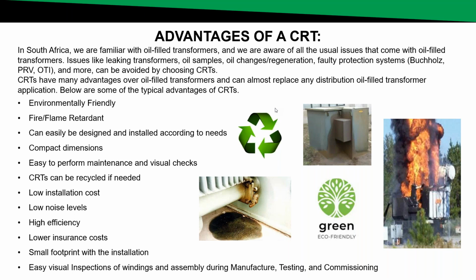Cast resin transformers are designed and manufactured to be flame retardant. As I've discussed, most cast resin transformers carry the F1 rating, which means they do not burn. I have even experienced personally where a complete installation has burned down. However, the actual cast resin transformer is still intact. You can still recognize the cast resin transformer due to its fire resistant properties.